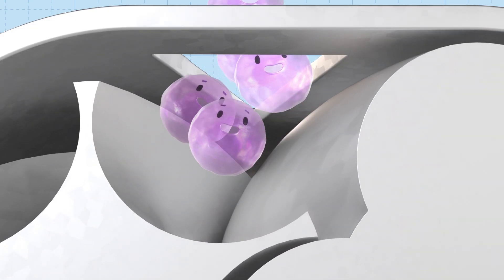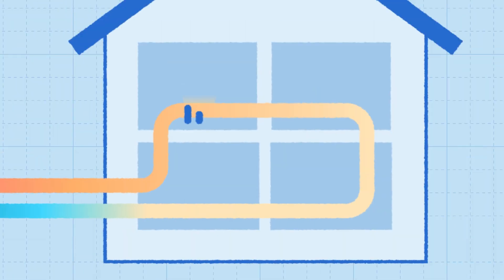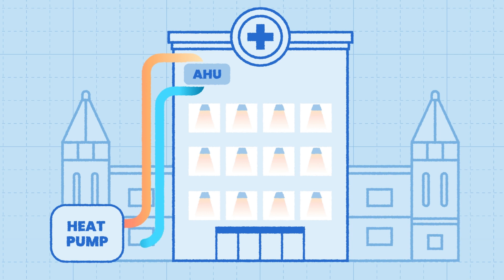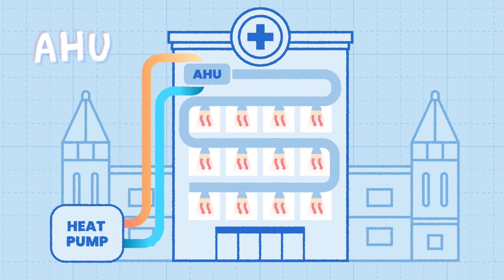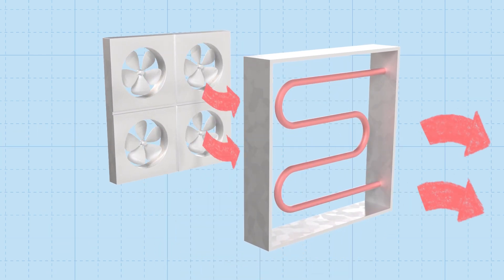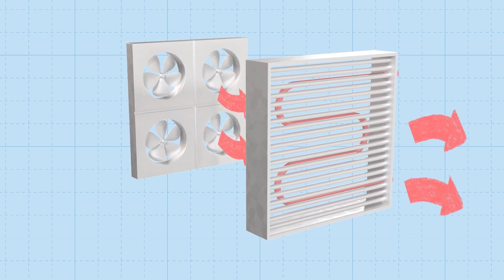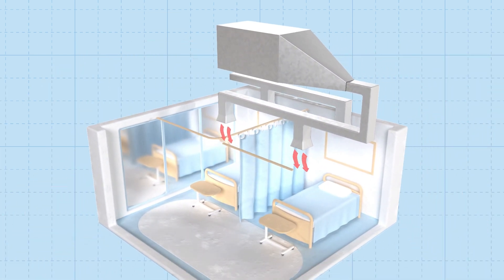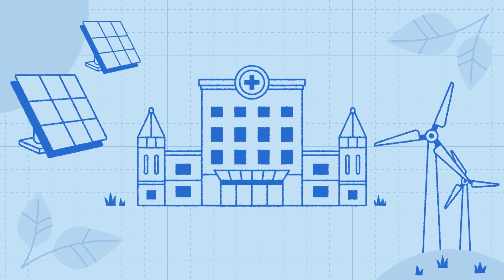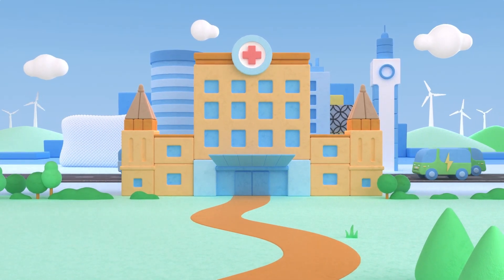The refrigerant gas then heads over to a different heat exchanger, where it passes on its heat to the water molecules that will run through the hospital. If this was a home, this water would then pass through radiators and keep it warm. However, in bigger buildings like our hospital, we might use air handling units instead of radiators. An air handling unit, or AHU for short, is a bit like a big hair dryer. Fans push the air along over a pipe that contains the water we've heated. The pipe snakes back and forth and has thin metal fins attached to it to help transfer the heat from the pipe to the air quicker. Once the air is warmed up, it moves through hidden tunnels, called ducts, to the spaces where the people are to keep them warm. And this whole process is powered by electricity produced from renewable sources, without burning any fossil fuels — so there's no extra cost to the planet. We can keep heating our hospitals in a sustainable way for generations to come.